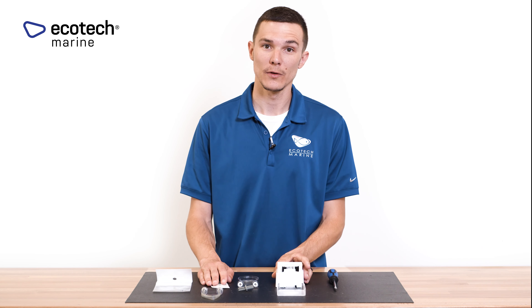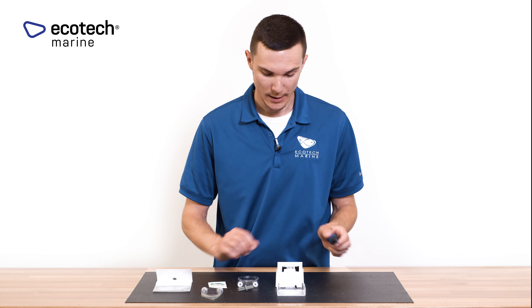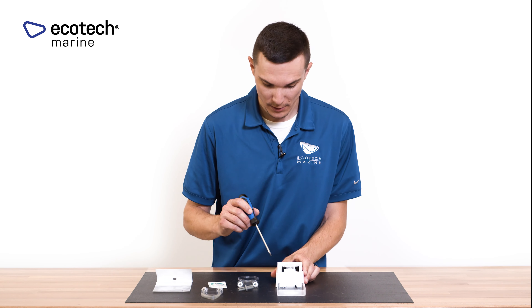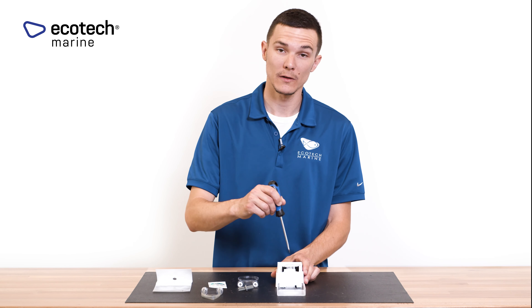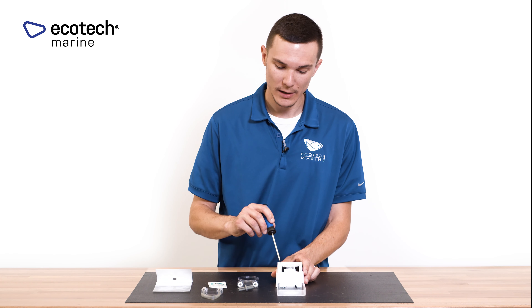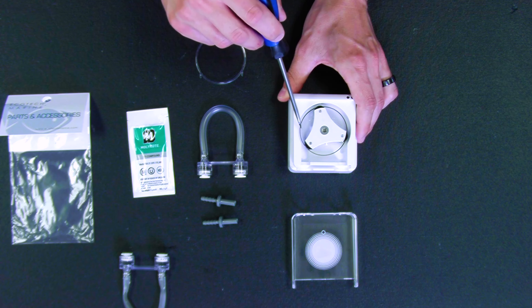You do not need to use the whole tube — just a small dab in each of these points. The pump is going to rotate in a clockwise motion based on the way it's designed, so you want to apply a small dab of grease on the forward side of each of the rollers.